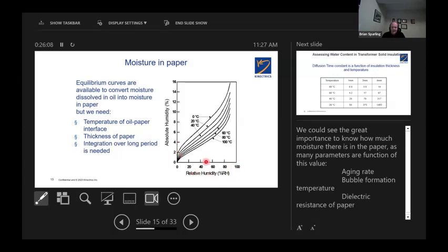If humidity of the oil is 60%, and the winding hotspot temperature, that's what we're looking at here, is 100 degrees C, you're really wet by this point. You're at 4.5. Anywhere between 3 and 4, 3.5%. My feeling is between 2.5% and 3%, 3.5% is the maximum you want to be at to avoid things like bubbling and also reduce the aging rate. That's the chart.